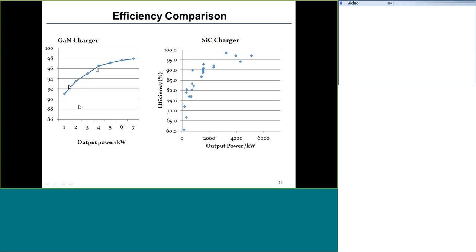This approach we adopt here actually gives us some pretty interesting phenomena. The efficiency number you see is not like most chargers reaching peak in the middle while dropping at the two sides. This charger's efficiency will always go up as power goes up, simply because when we run at low power, the switching frequency is higher, so the power loss will be big. While when we run these two chargers at heavy load, the switching frequency drops, so switching loss is actually reduced.